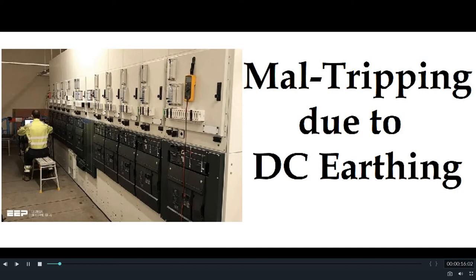When there is a tripping in the substation and we don't get any reason or logic for the tripping, then we call it mal tripping or sometimes spurious tripping. There may be a thousand reasons for which the relay or the circuit breaker may mal trip. But today I will discuss the mal tripping which occurs due to DC earth fault.